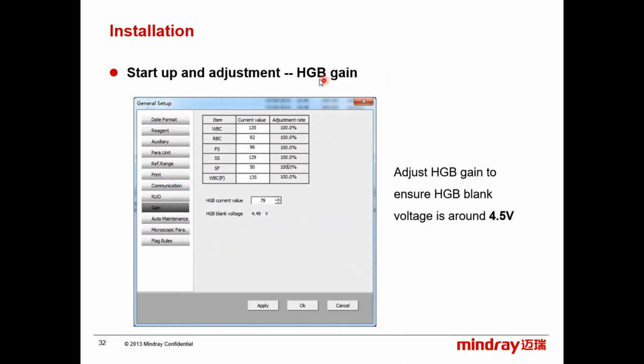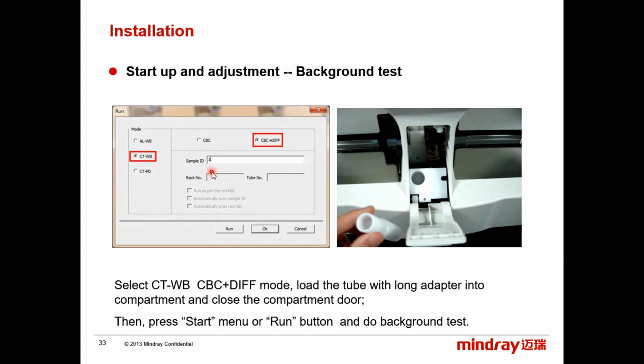All right, this hemoglobin blank voltage adjusted to 4.5 approximately. All right, this is very important. Just play with this gain. This one, what it will do, it will just adjust the blank voltage. So there is liquid inside the WBC bath. It will turn on the LED and it will measure the voltage. It should be around 4.5. All right.